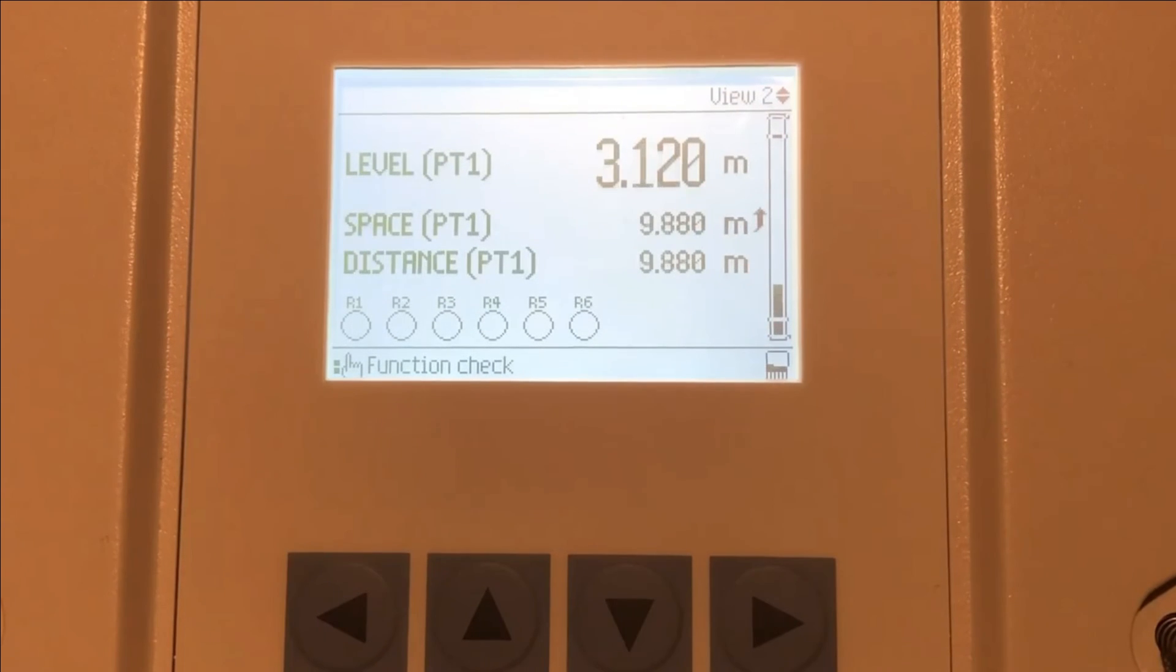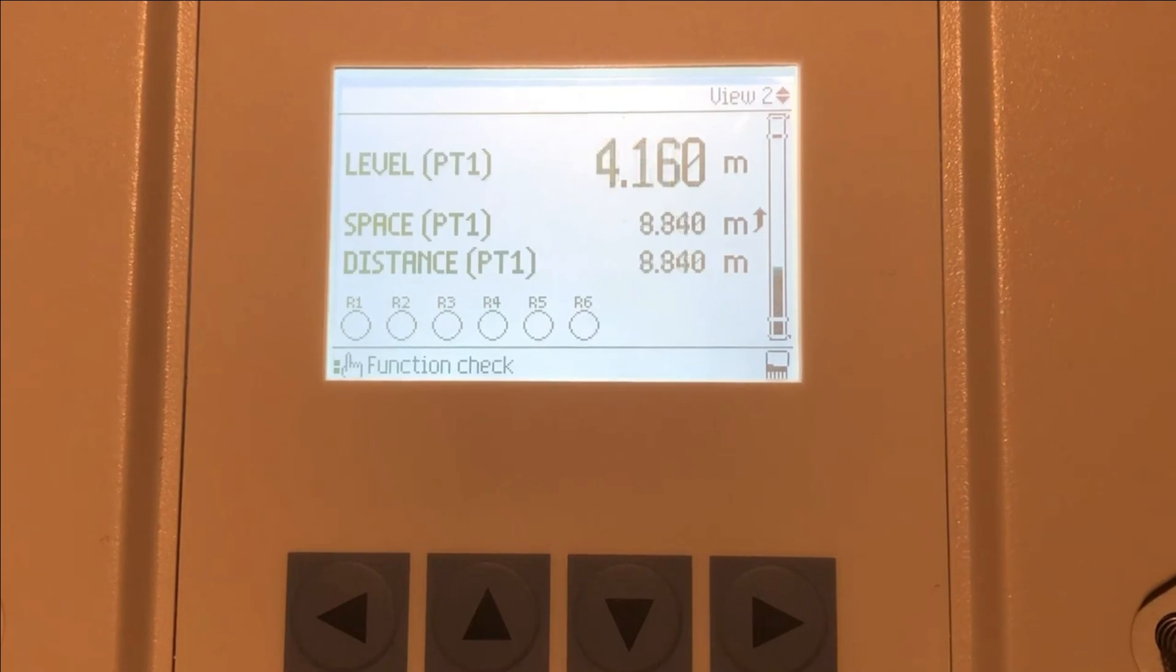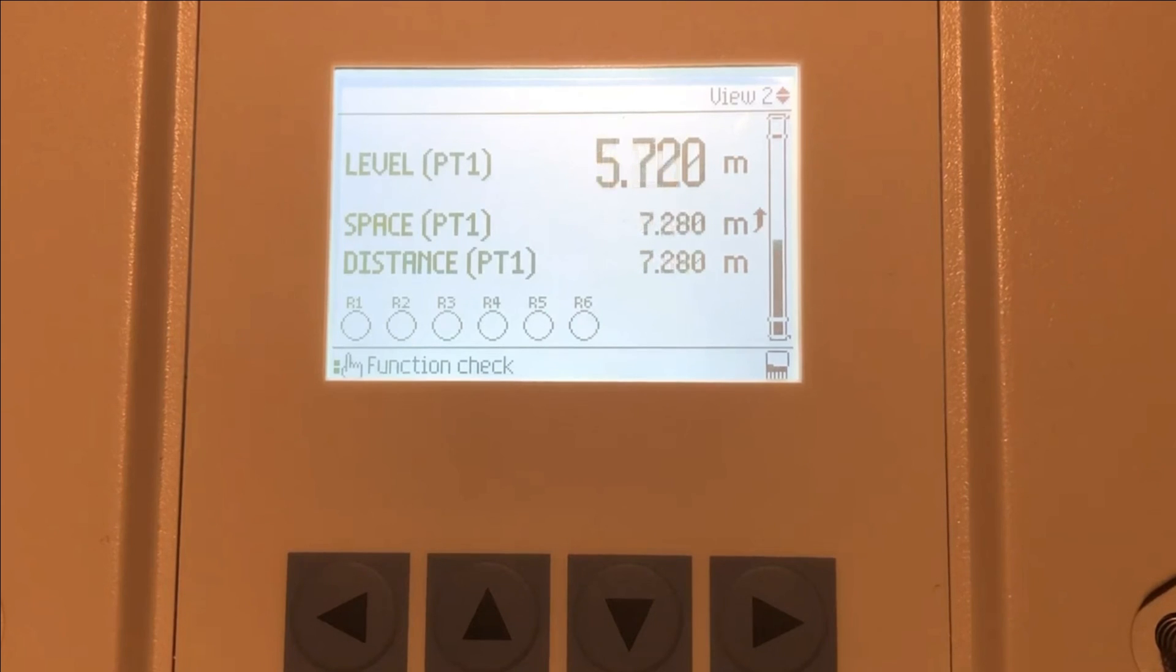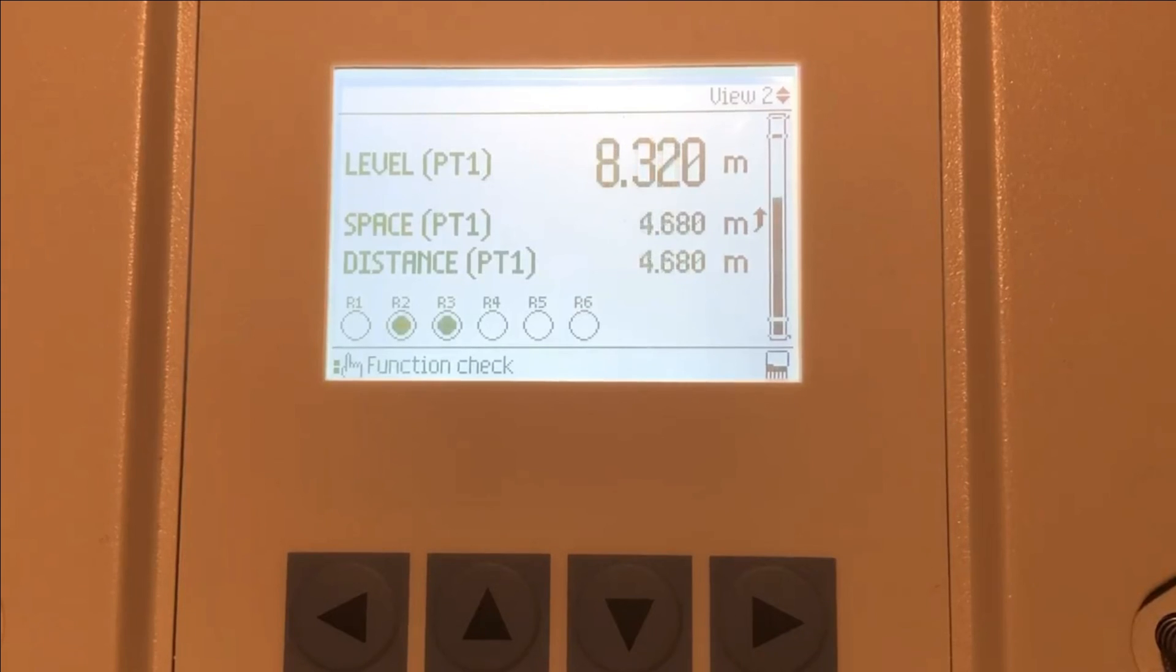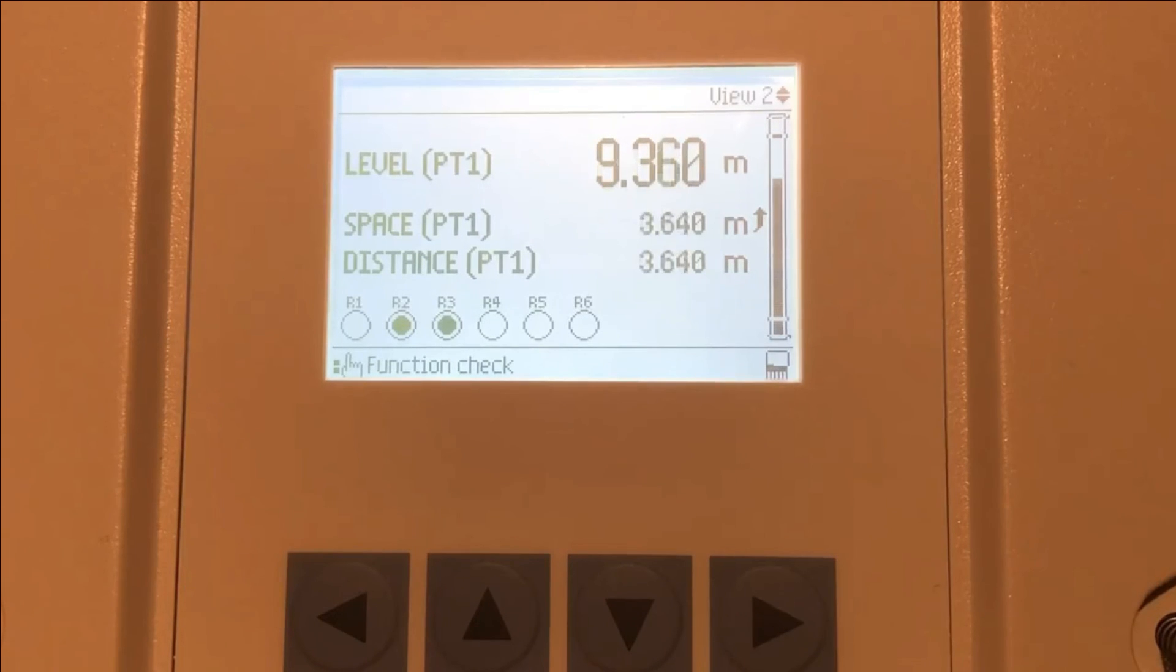So we can go back to our top level view and our simulation will have already started. So we can see as we come up to six meters of level, our first pump will turn on as that's our first set point. And as we move on to eight meters, our second pump will turn on, followed by our third pump at 10 meters.